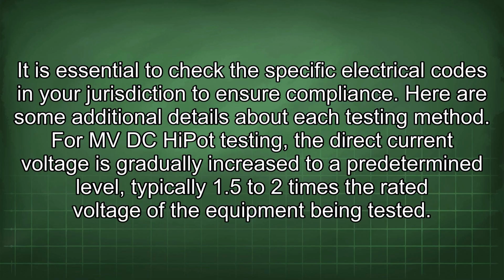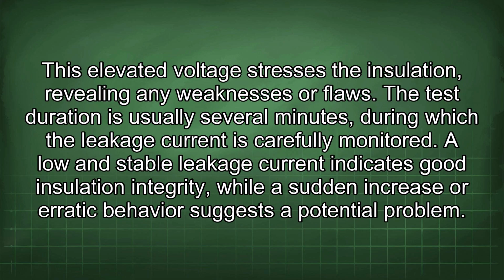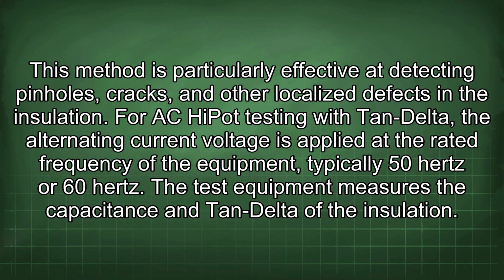Here are some additional details about each testing method. For MVDC HiPot testing, the direct current voltage is gradually increased to a predetermined level, typically 1.5 to 2 times the rated voltage of the equipment being tested. This elevated voltage stresses the insulation, revealing any weaknesses or flaws. The test duration is usually several minutes, during which the leakage current is carefully monitored. A low and stable leakage current indicates good insulation integrity, while a sudden increase or erratic behavior suggests a potential problem. This method is particularly effective at detecting pinholes, cracks, and other localized defects in the insulation.